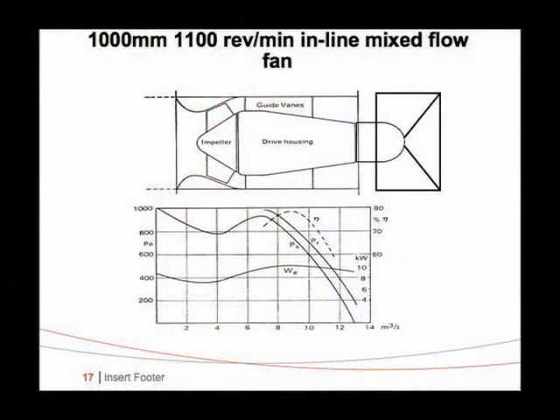And then as a design build engineer, I need to look at all the details. And without spending time on this, you can see that the aerodynamics on the dampers is bad. The edges of the casing are folded inward to catch the airstream. I don't know why. And then you look at the outlet of a mixed flow fan, and it comes out through this annulus at very high velocity, which is losing your static pressure. Don't understand your velocity pressure. This is bad, and high turbulence.